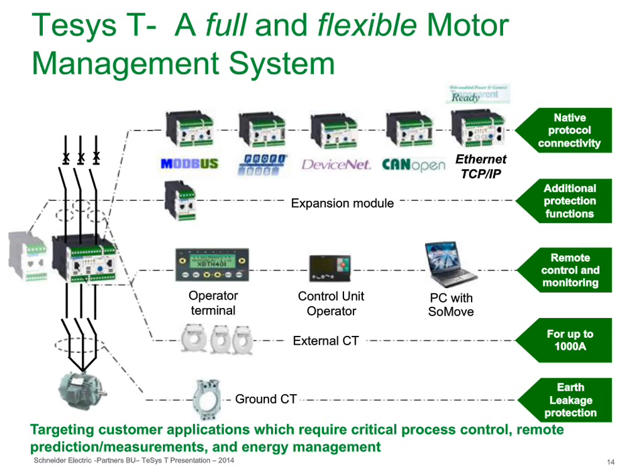We talked a little bit about the fact that we can do remote monitoring with many HMI devices, as well as hook up to PCs or other controllers. But again, if we do have over 100 amp requirements for motors, we can put external CTs that do hook up very nicely to the TeSys T. And we can do grounding either by using phase imbalance with the external or internal CTs, or we can put a single ground CT that we can do phase imbalance, phase loss, phase reversal, all those phase functions and ground functions with a ground CT here as well.